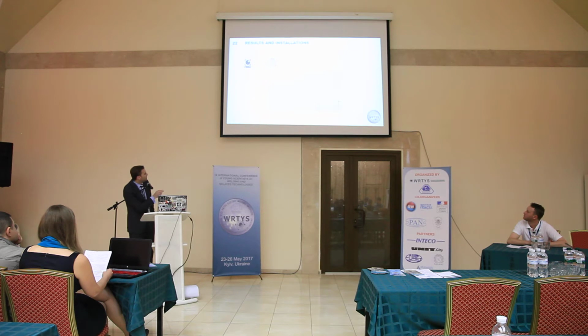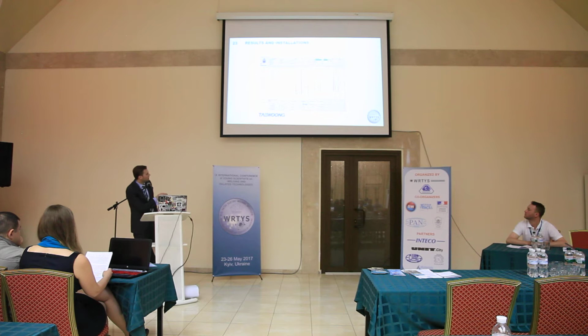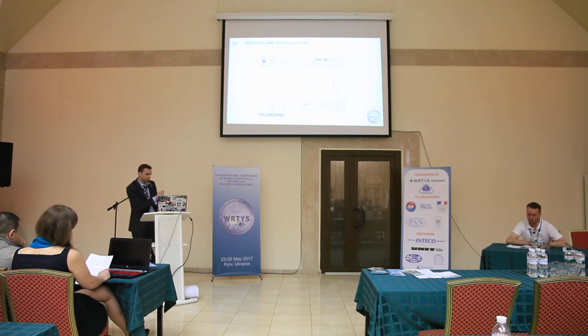The hydrogen content, as you can see here, we predicted this value compared to the measurement at the end, also pretty close. So you see the result of the online simulation goes directly into this new level 2 system. Compared to this, you can see directly on the HMI, on the old system in South Korea. But at the end it was the same results. We installed our modeling library, they called the API, and got also the temperature curve in that system.